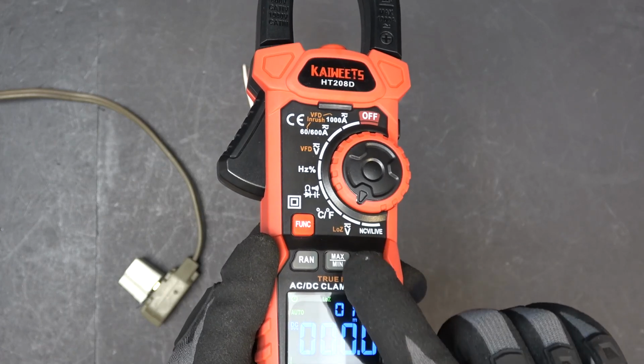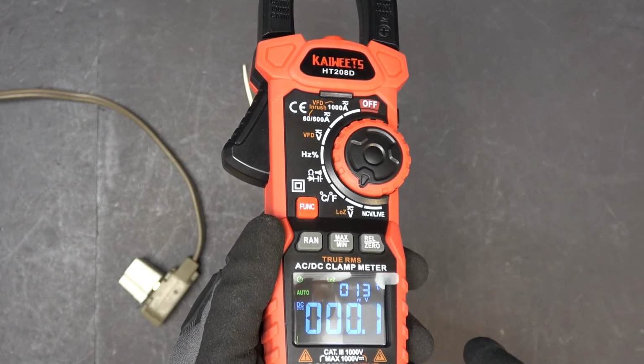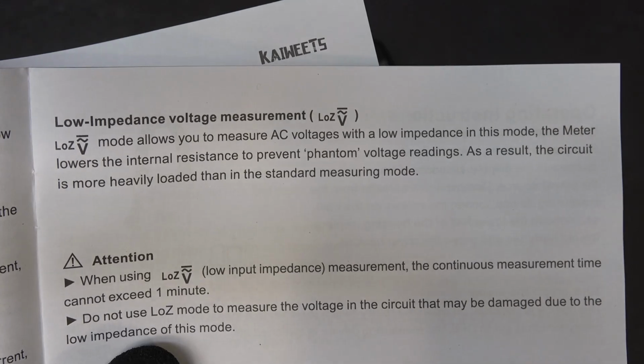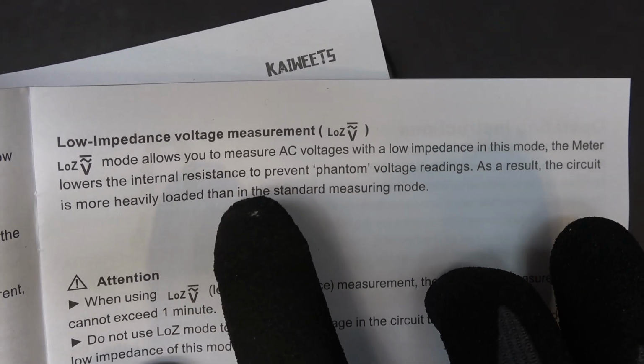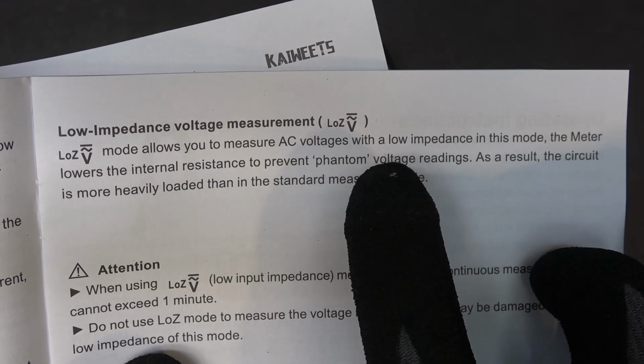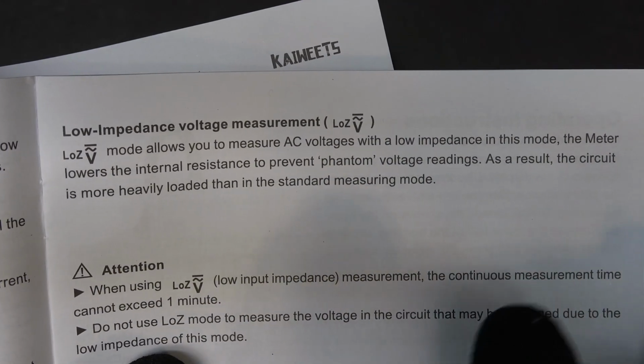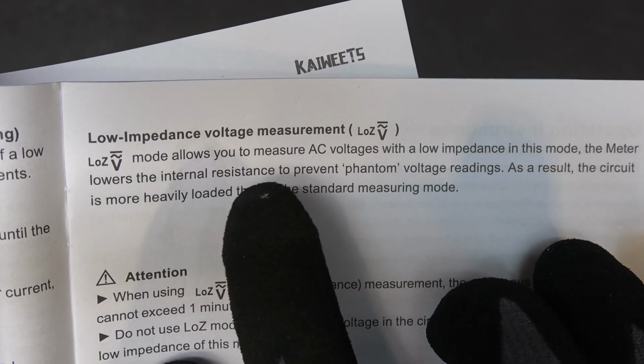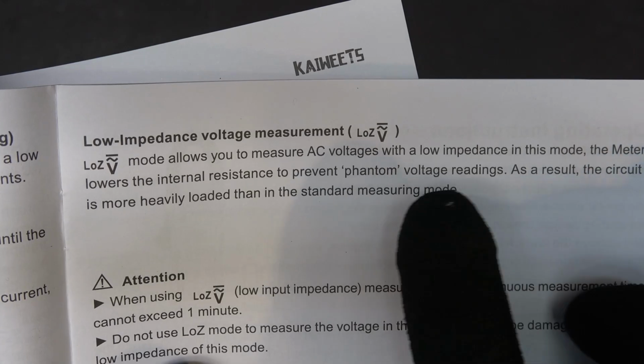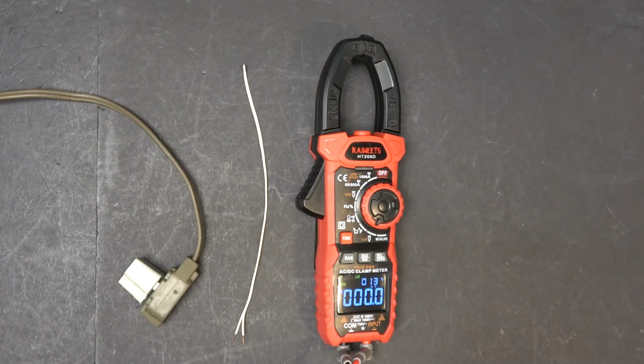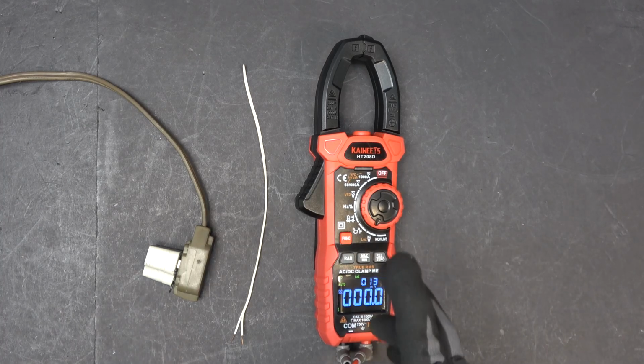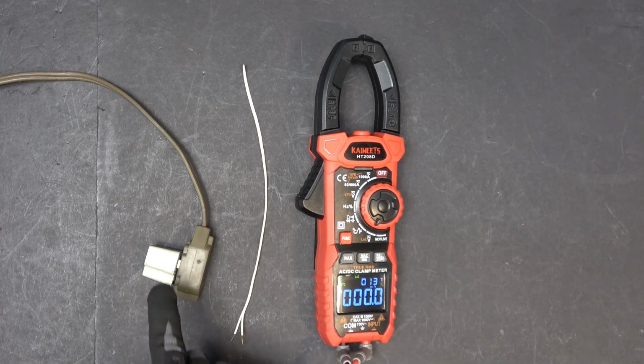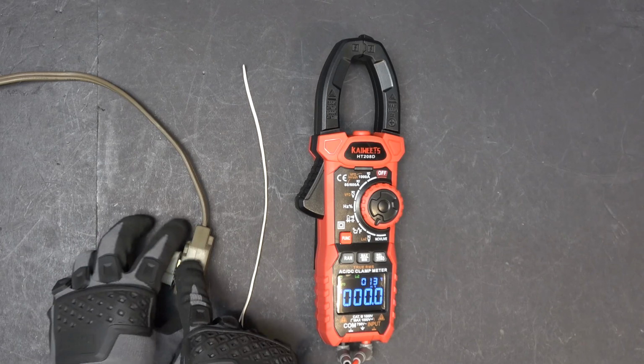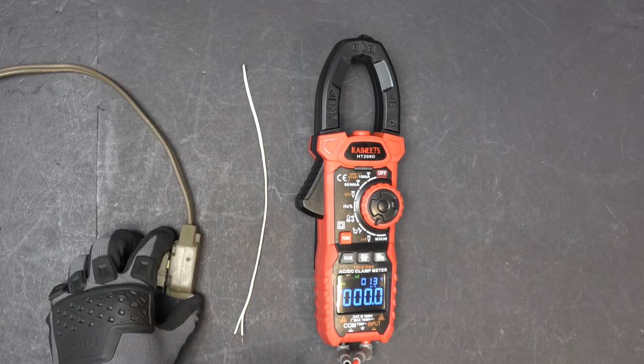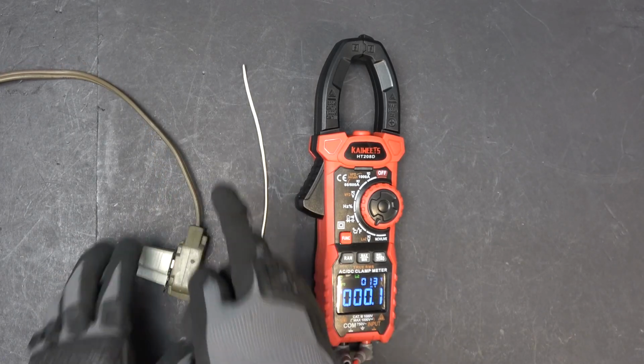Next, I want to talk about the low Z voltage reading on the meter. According to the user manual, low Z allows you to measure AC voltage with a low impedance. So the meter will lower the internal resistance to prevent phantom voltage reading or ghost voltage. Let me give you an example to make it easier to understand. I have a live 120 volt AC outlet here and just a bare wire right next to it.